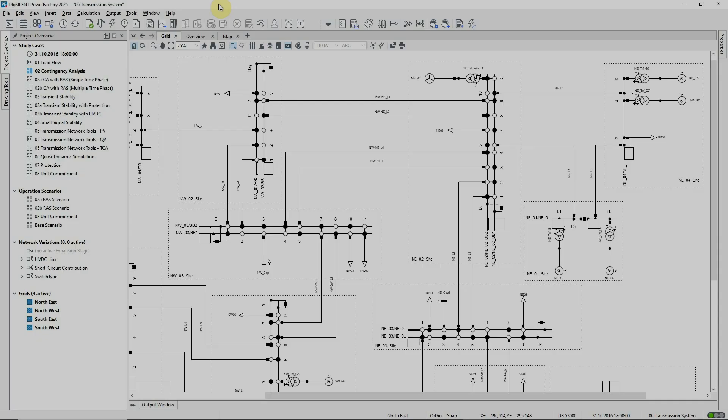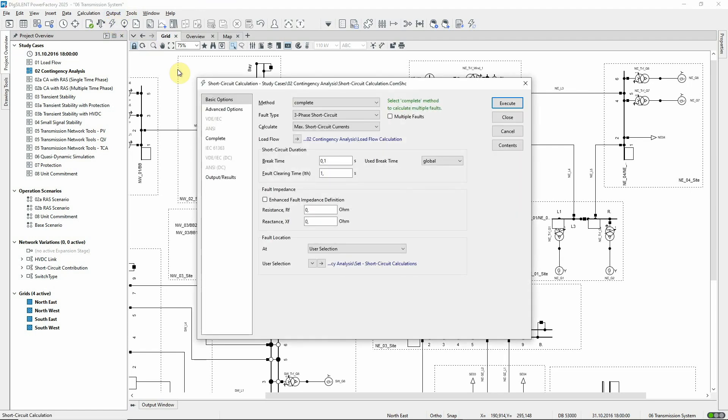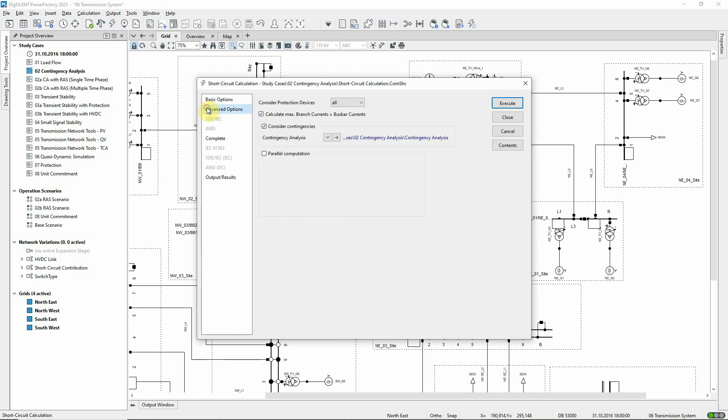In PowerFactory 2025, the short circuit calculation now has an option to be executed for selected contingency cases. This is useful, for example, if post-fault short circuit infeeds need to be assessed for protection purposes, or to ensure that remedial actions do not result in unacceptable short circuit levels.